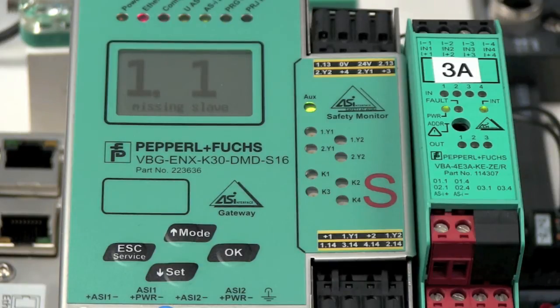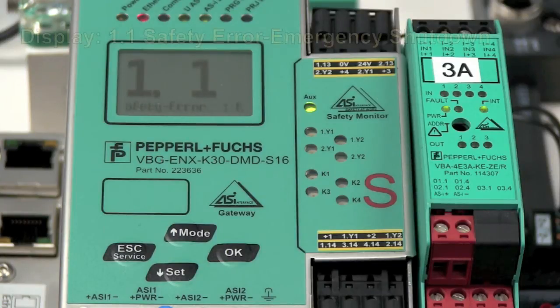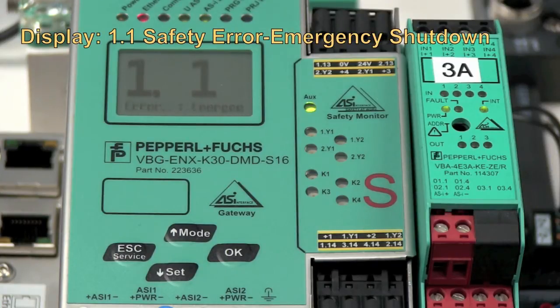The first thing that I will do without pushing any buttons is I will reconnect my replacement safety device. This will remove the configuration fault because now the network is complete, but we are still in error mode since the safety codes from the new e-stop are not the same as those from the old e-stop.